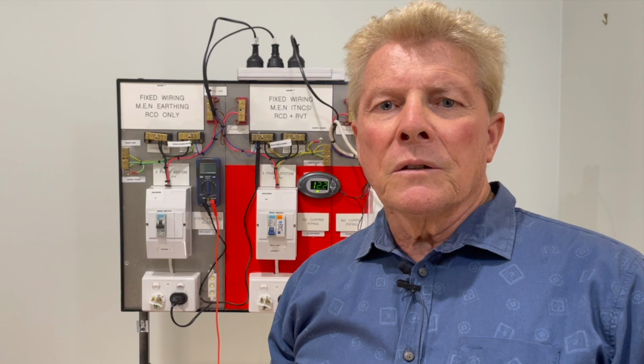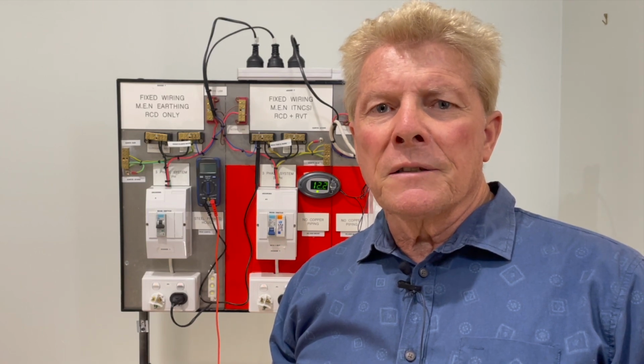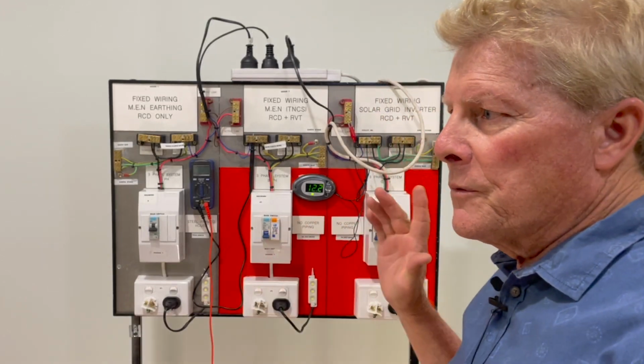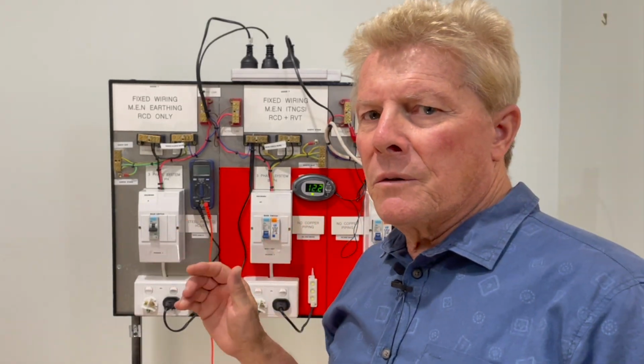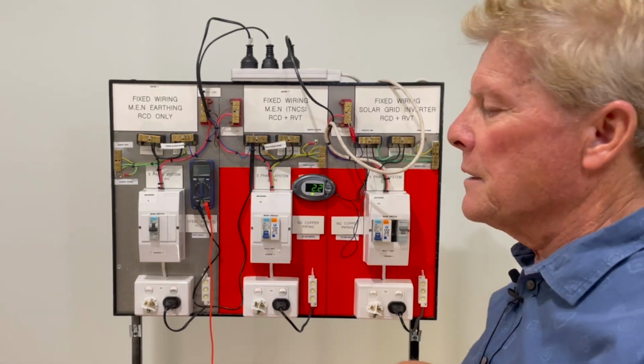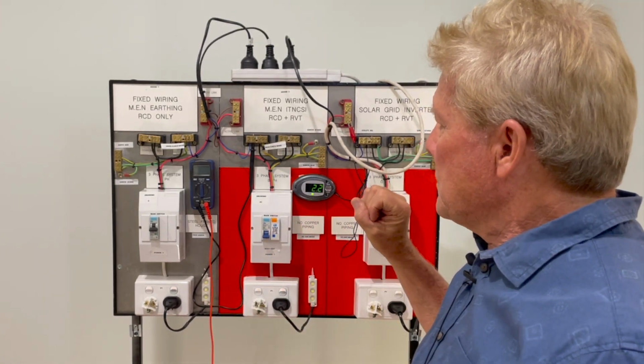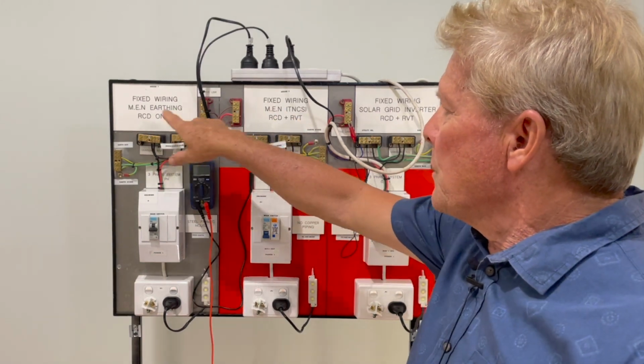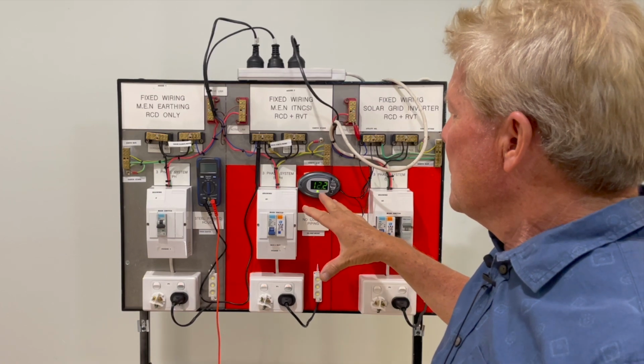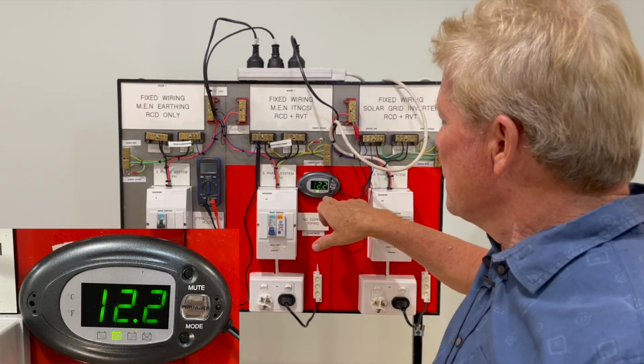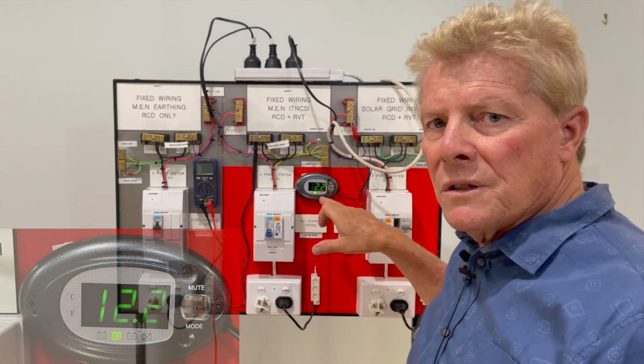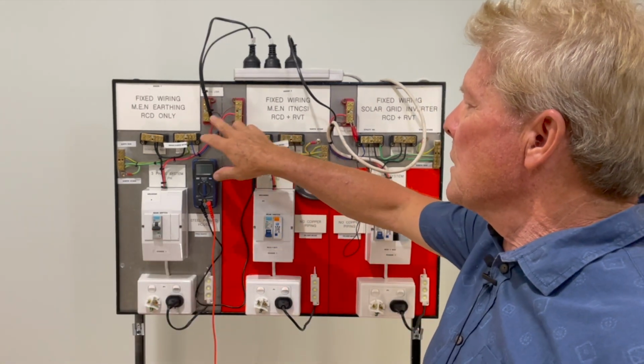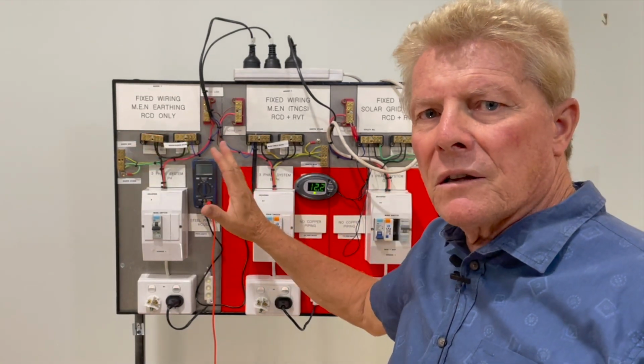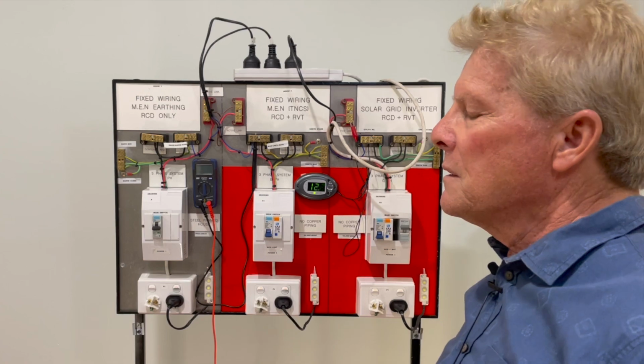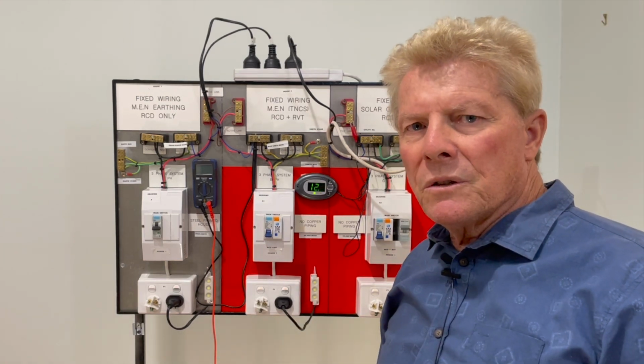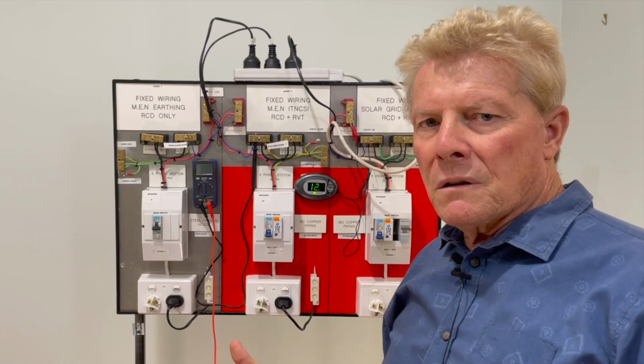Today's video is going to be on the loss of neutral in a three-phase MEN system using our verification panel that we've used in a lot of our research and documentation. This replicates the three-phase fixed wiring MEN earthing situation over 3 houses, but we're using a power supply of 12 volts DC. That's just because we've got all exposed actives and neutral links, so it makes it a lot safer. It still shows you what happens when you lose the neutral using the lower voltages.